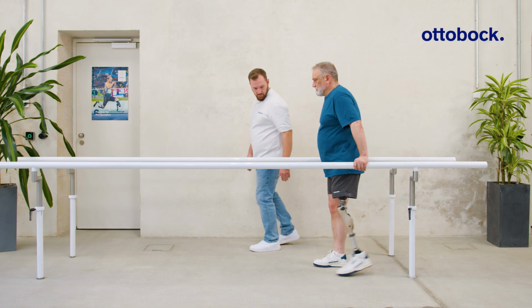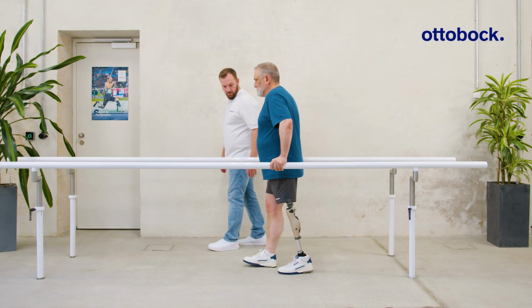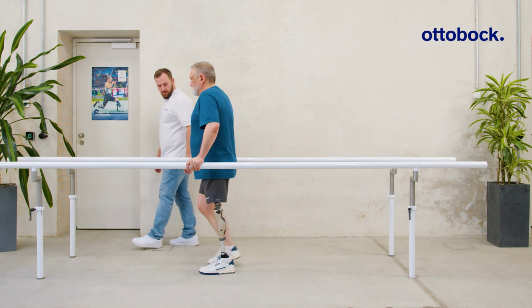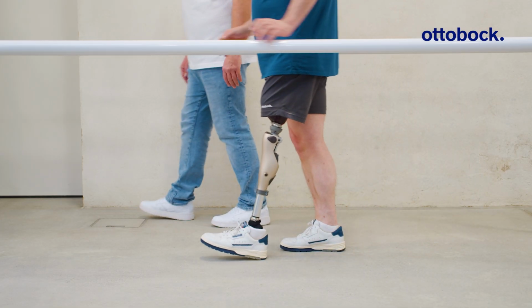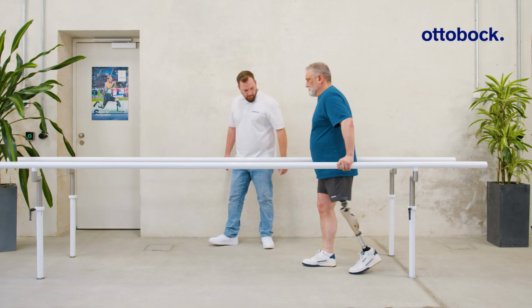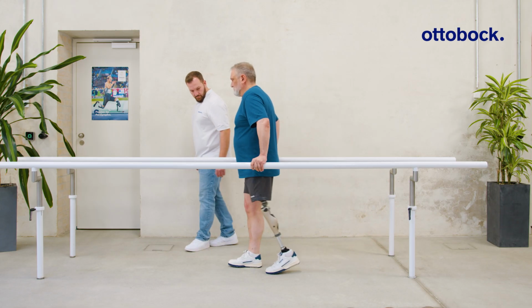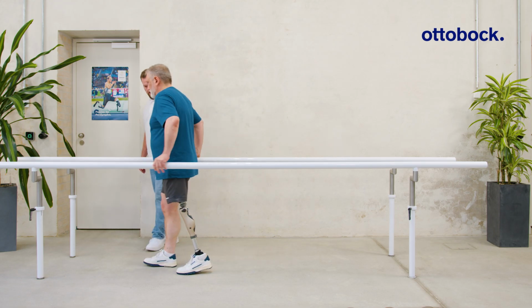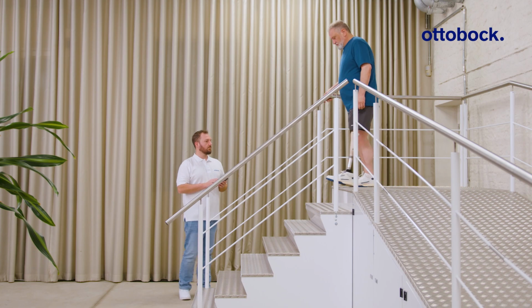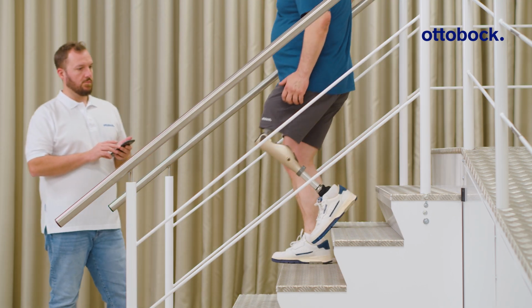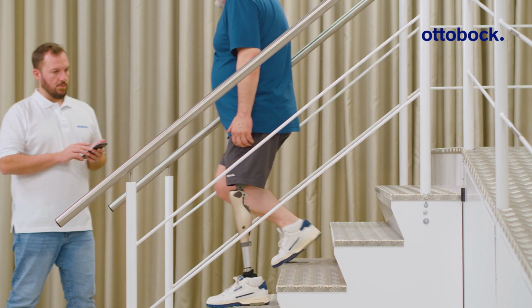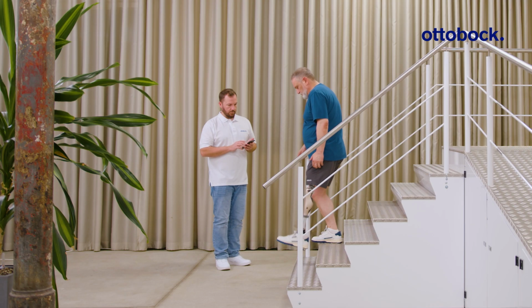Activity Mode C is suitable for users who are able to control unrestricted knee flexion during the stance phase. In this activity mode, the Kenevo does not lock but provides a high level of stance phase flexion resistance. Stance release occurs earlier than in the activity modes B and B+, promoting a more dynamic gait pattern.